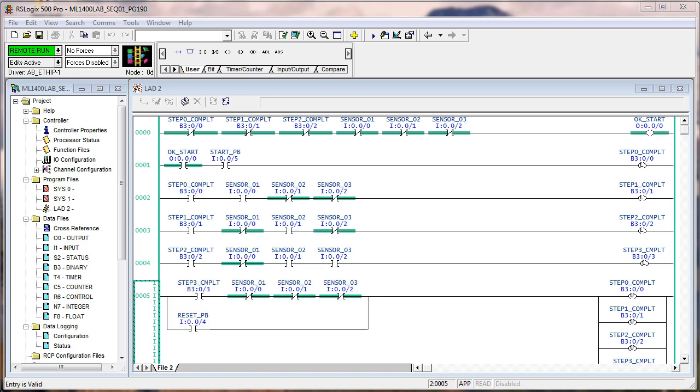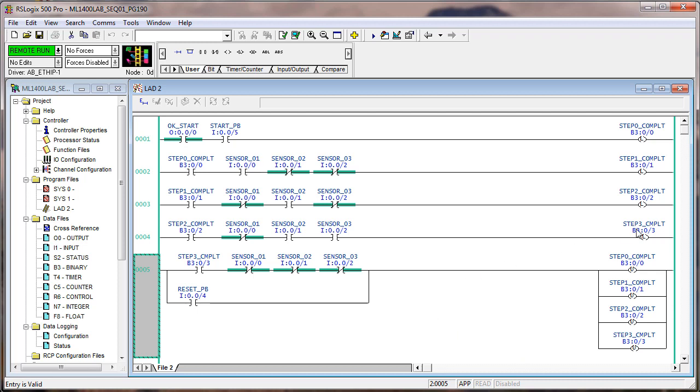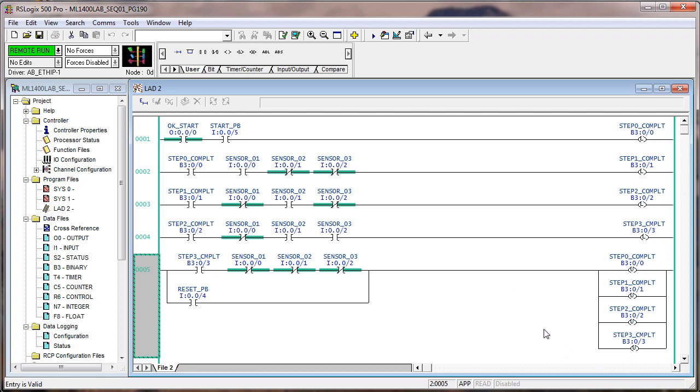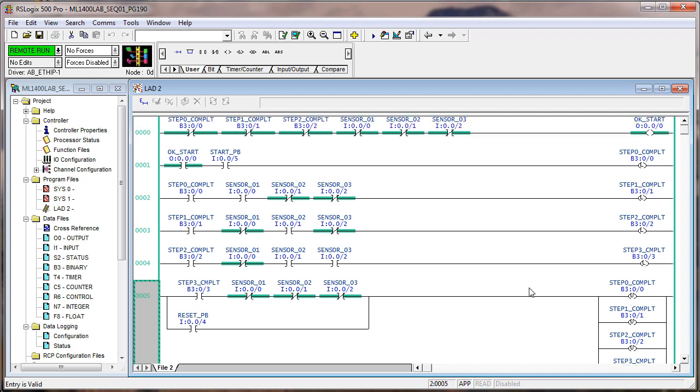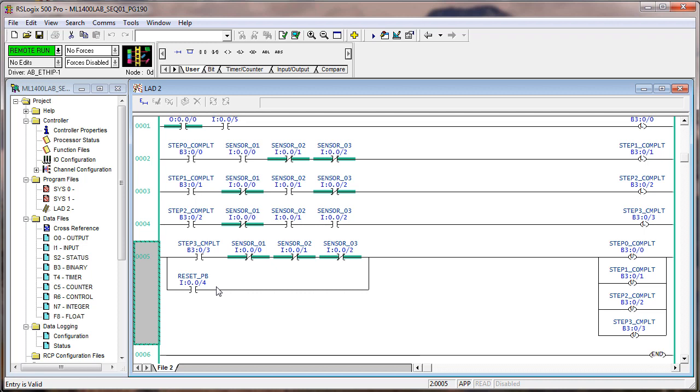Going a little further here, we took step three complete and we replaced the reset push button with step three complete. So when step three is complete, it unlatched the complete bits, which would have made this true again, and you would have went back to okay to start if the sensors were in the right position. Then we added the sensors have to be in the right position in order to reset the sequence. And then we put the reset push button back in as a method for the operator. If they cleared the machine and got everything back in the right position, they could hit the reset button to clear the logic.